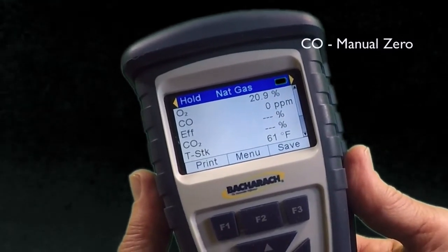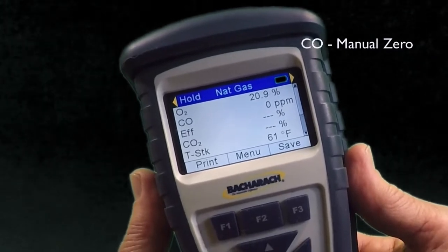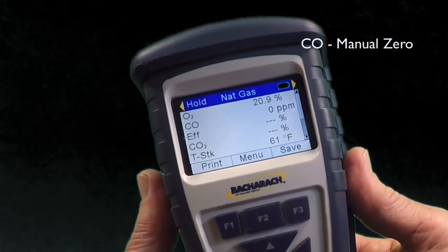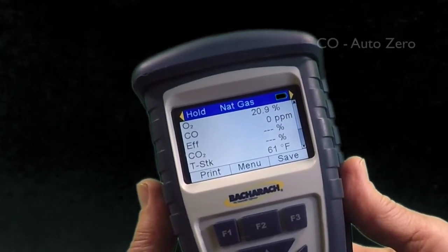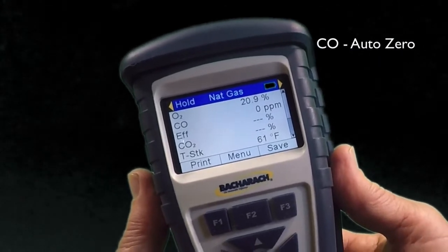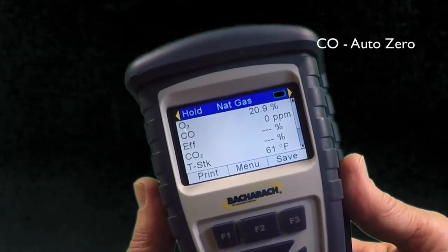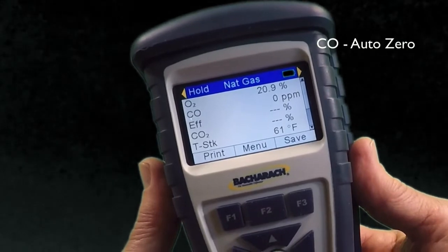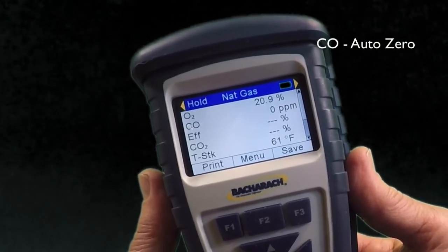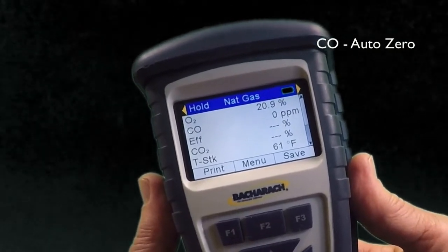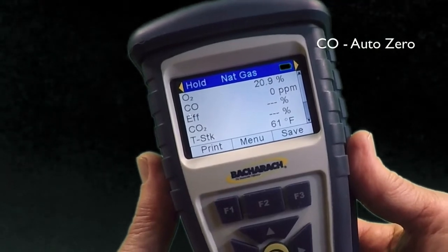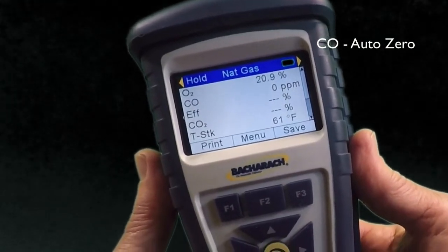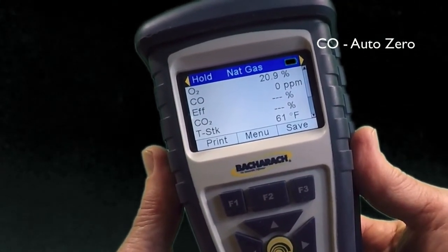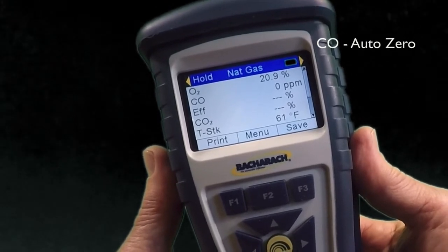A safety concern. All other manufacturers do what's called a CO auto zero, and that's how Bacharach ships their instruments. If you haven't changed it, yours is probably still set up to do an auto zero. An auto zero means that the instrument assumes the air sampled during the warm-up is clean, and it will display 0 ppm when it's finished, even if there's somewhere between 1 and 49 ppm in the air where you're at.